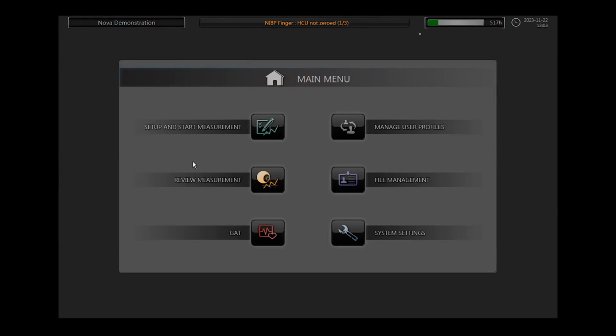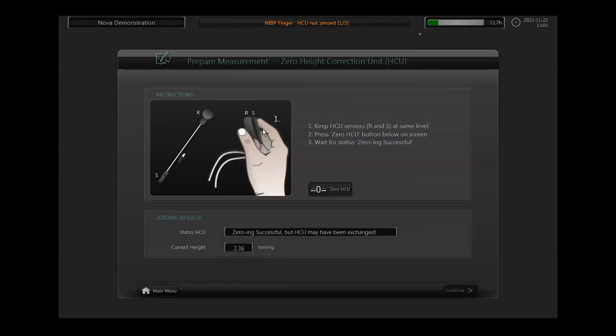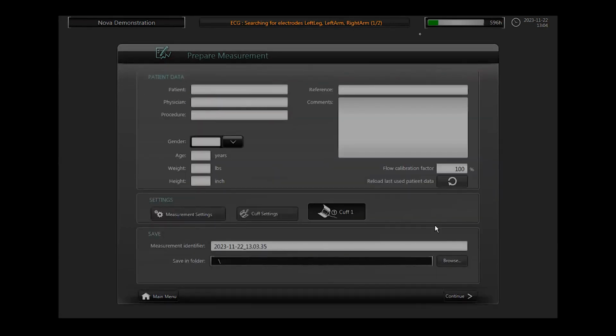Get started taking a measurement. Select the Setup and Start Measurement button. If the height correction unit has not been zeroed, you will be prompted to complete this step. With the 2 sensors connected as shown in the picture, select the Zero Height Correction Unit button. As a reminder, the height correction unit allows for subject movement while still maintaining accuracy. Next, you can enter patient information. A few important notes. Reload last used patient data button is very useful. This shows the information that is required to be entered. There is also space to enter any pertinent comments.